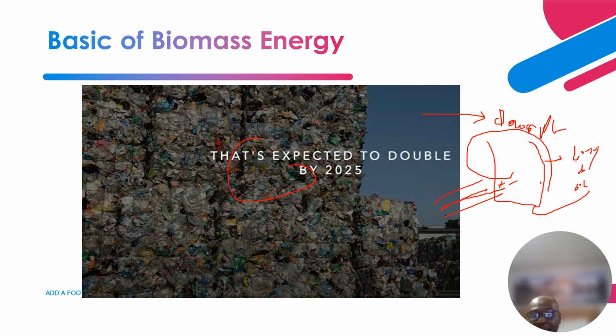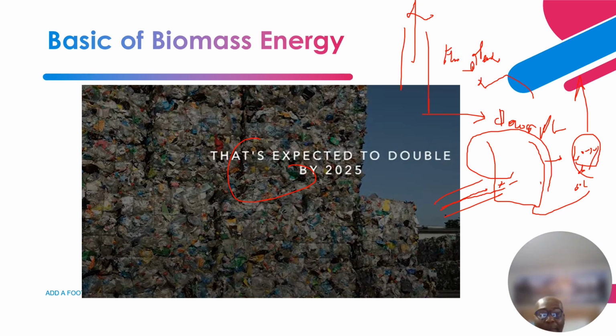The dry steam rises up and goes through a reheat section, where another means of heating is used. Usually they utilize the heat from the exhaust that goes out into the atmosphere. There's a tower right there, and they call it flue gas, from the burning of this trash. Part of the heat from the flue gas is taken and fed through the reheater pendants.